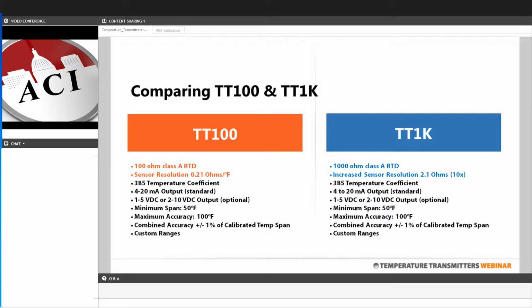Both the 100 ohm and 1000 ohm RTDs have the same level of accuracy. They follow the same temperature curve and are available in the same types of outputs. Because the TT1K offers that higher level of resolution, we generally recommend using it when you have the choice or the option of picking which one. And also because of that higher level of resolution, the TT1K is available in all of our standard configurations, and there are a couple configurations of the TT100 that aren't available just due to that lower resolution.